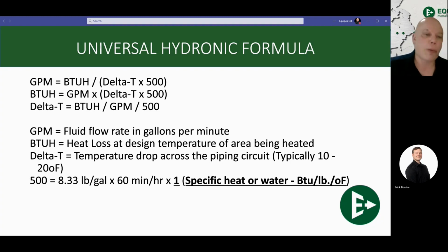BTUs, how do we calculate how many BTUs are getting delivered? BTU equals GPM multiplied by delta T times 500. So here's a bit of basic math: brackets, exponents, division, multiplication, addition, and subtraction. So you will have to do the brackets first on a couple of these. But that's your standard mathematics. So to calculate how many BTUs are getting delivered, you use this formula. And again, your delta T is between 10 and 20 if it's in-floor or a standard heat emitter. Now that last one that we have here: delta T equals BTU divided by GPM times 500. And that's how you can calculate what your delta T is inside of a system.